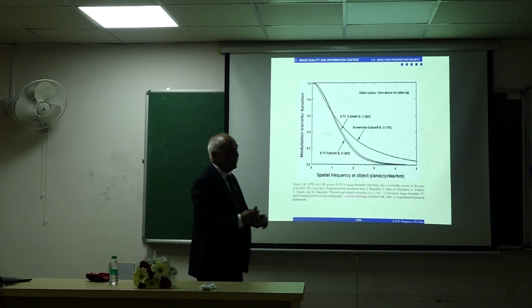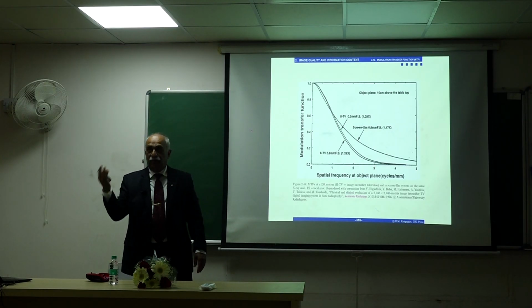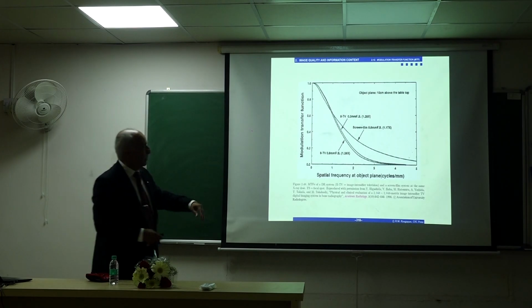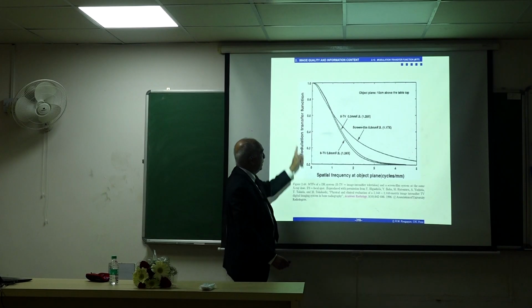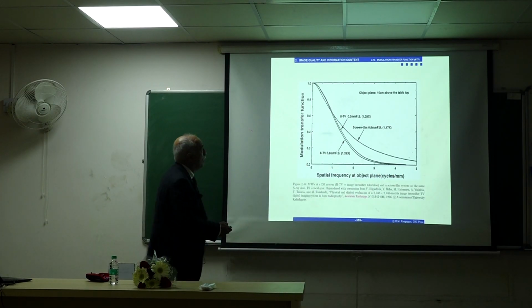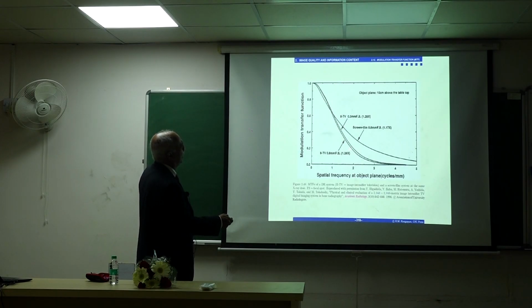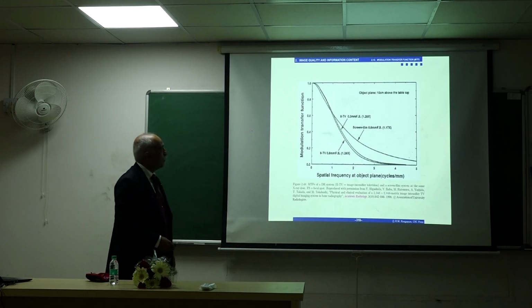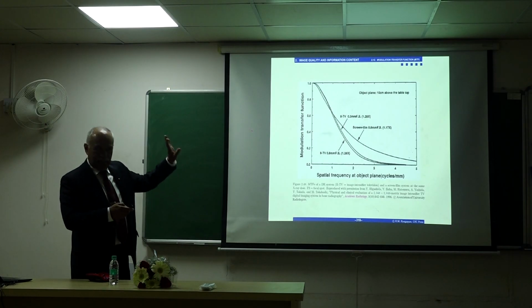And FS is focal spot. I mentioned earlier, if the focal spot in the X-ray tube is too large, there is blurring. So they are comparing here. This is image intensifier TV with 0.8 millimeter focal spot and with 0.3 millimeter focal spot, and this is screen film. Obviously, screen film was at that time better than the digital. More area under the curve. This is normalized 1 up to 5 cycles per millimeter. Here, the two of these digital systems are fairly close. There is not much of a difference, but there is a small difference. The larger the focal spot, the more the low pass. The area is reduced a bit. Okay? So all of these, as I said, are important in practice.